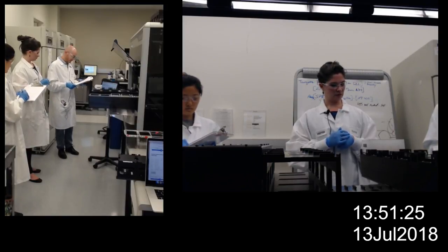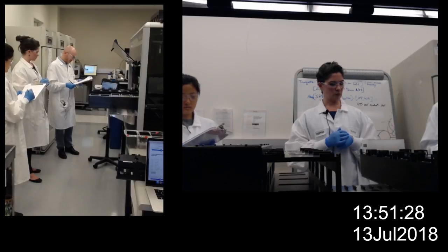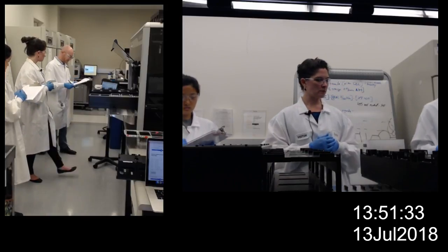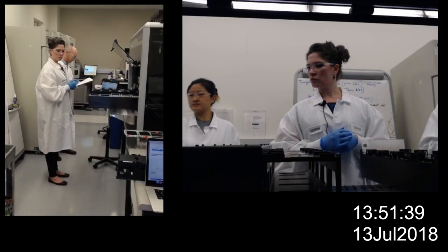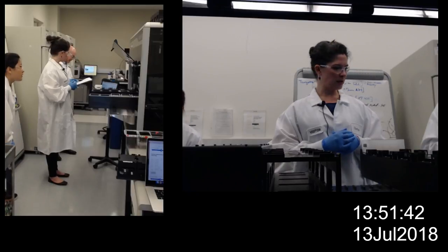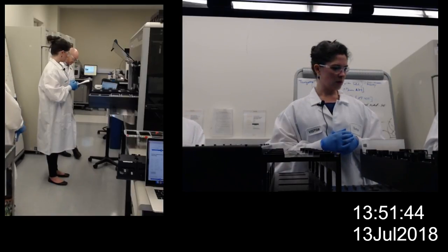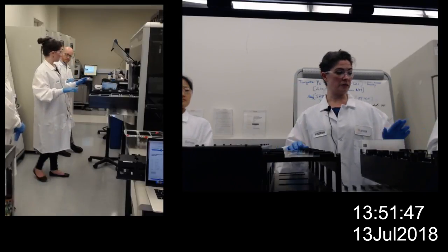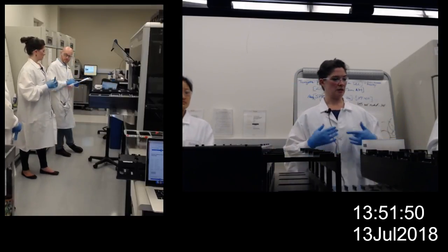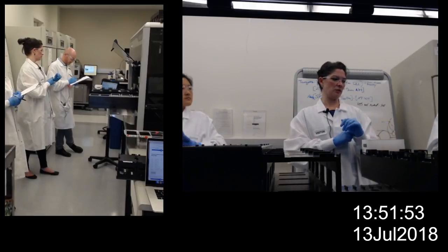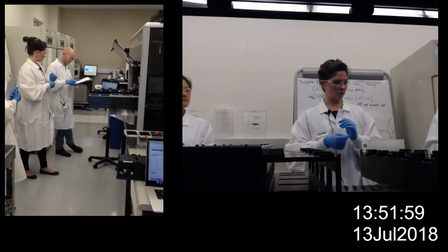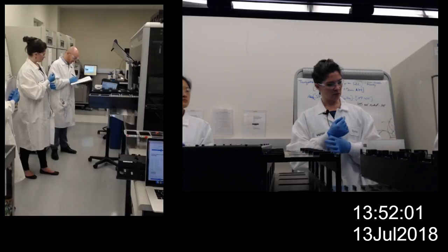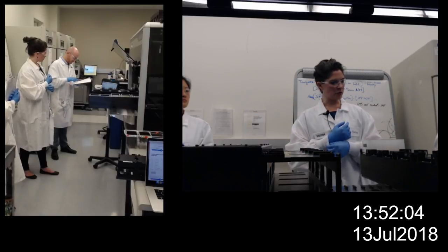What are your overall thoughts about unloading the consumables and, yeah, just kind of in general through this whole setup or scenario? Tubes, tube racks, tip rack. In terms of actually interacting with the Hamilton, everything seems really clearly explained. I think I would want to make sure I had whatever I was storing those remainder samples in ready to go. But yeah, there's nothing I find confusing about the unloading process there.